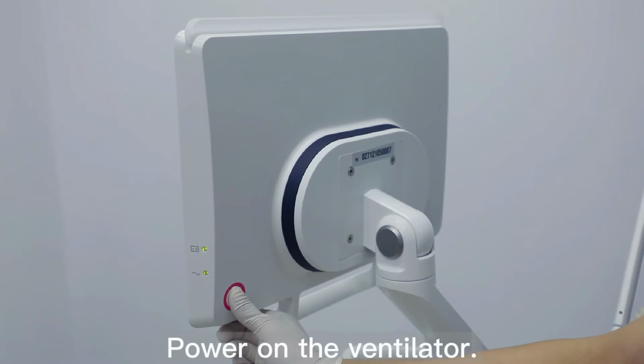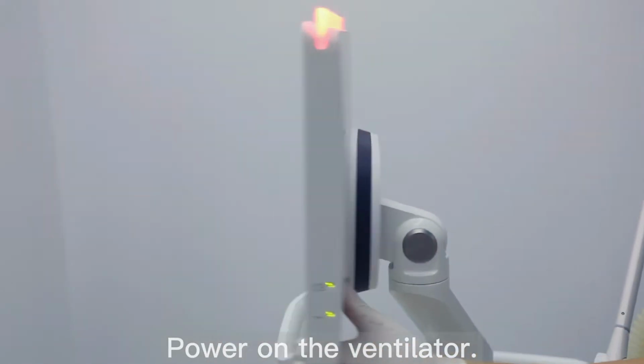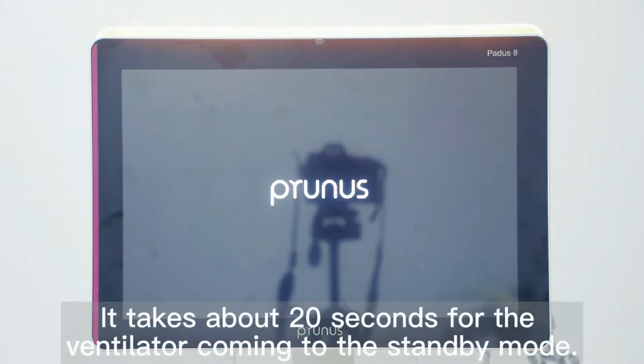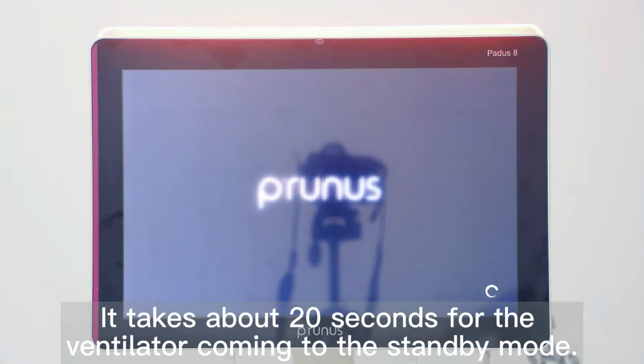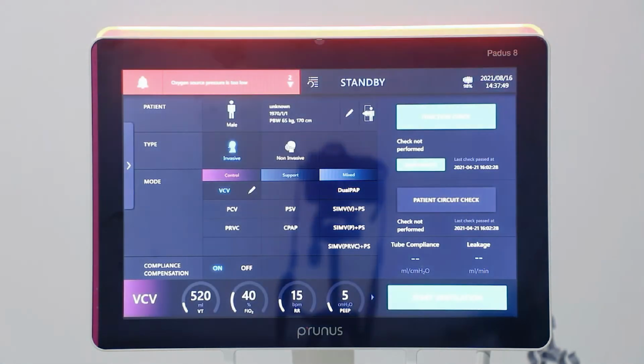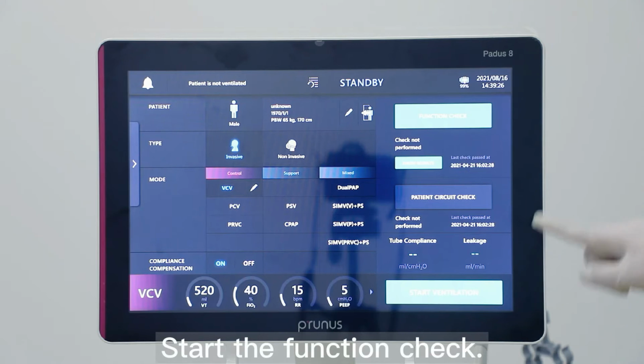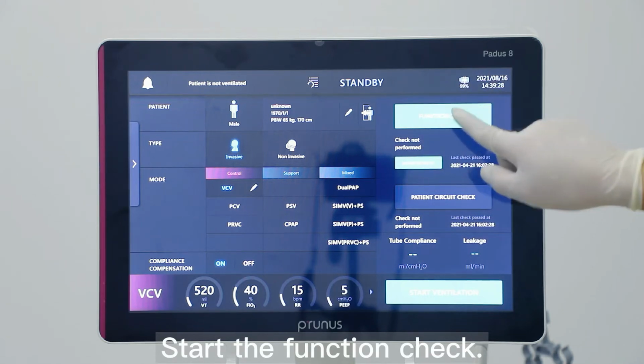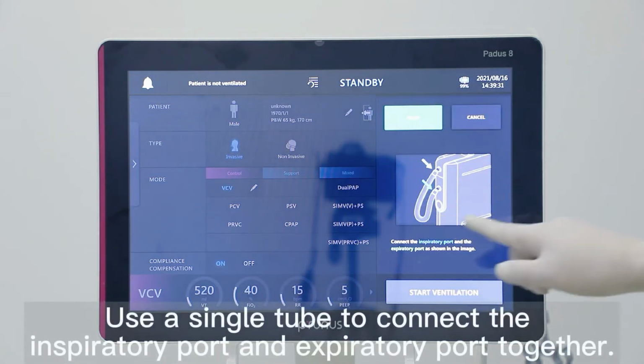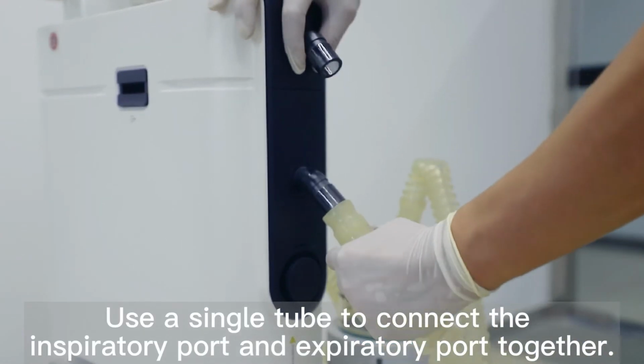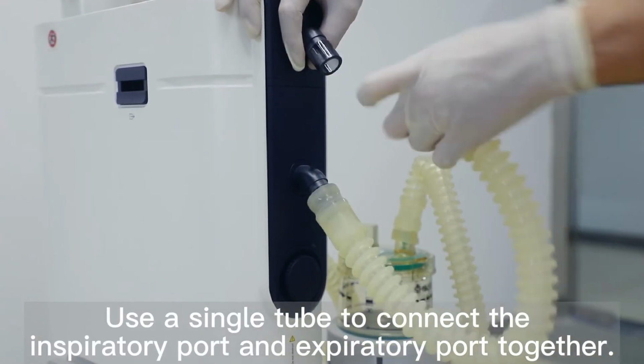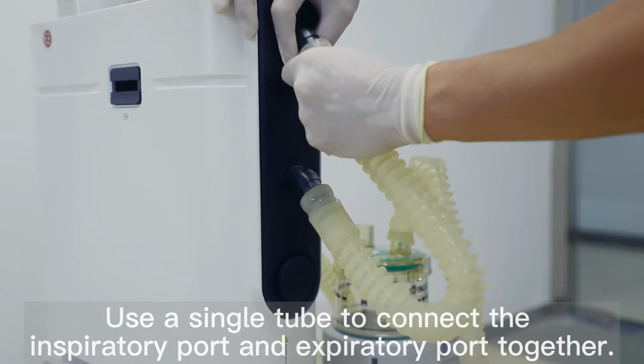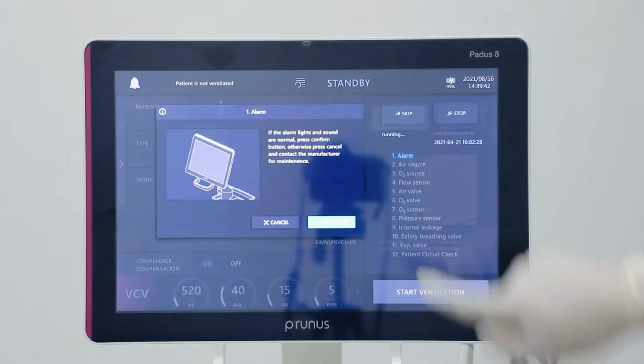Power on the ventilator. It takes about 20 seconds for the ventilator to come to the standby mode. Start the function check. Use a single tube to connect the inspiratory port and expiratory port together. Click Start.